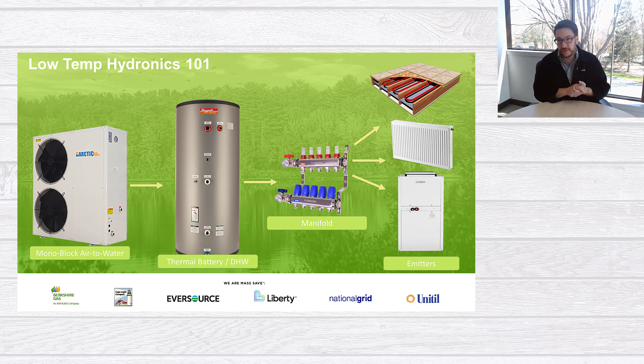From this thermal storage system or buffer tank, it's going over to a manifold. And from the manifold, that's where air-to-water gets really exciting. There's a lot of different ways that you can connect it and configure it. So you can connect it to a radiant floor system. You can be connecting it to a European-style flat panel radiator. You can be connecting it to a fan coil air handler, that's the same as what you would see with a hydro air system. So with air-to-water, tons of flexibility. You can mix and match different emitters, and you can have the benefits of heating with hydronics, which is quieter, less dust, all through an air-to-water heat pump. So it is really exciting.